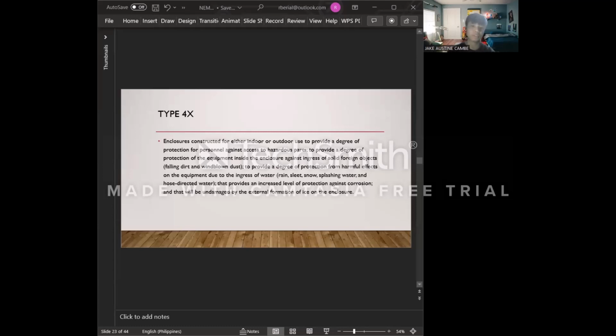Next type of enclosure is type 4X. So, type 4X enclosures are constructed for either indoor or outdoor use to provide a degree of protection for personnel against access to hazardous parts. Next is to provide a degree of protection of the equipment inside the enclosure against ingress of solid foreign objects, for example, falling dirt and wind-blown dust, and to provide a degree of protection from harmful effects on the equipment due to the ingress of water, for example, rain, sleet, snow, splashing water, and hose-directed water. So that provides an increased level of protection against corrosion, and that will be undamaged by the external formation of the ice on the enclosure.